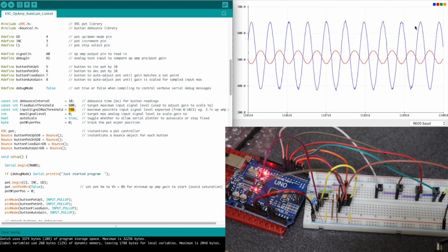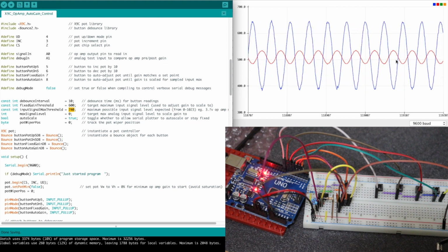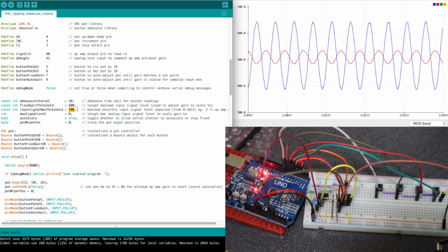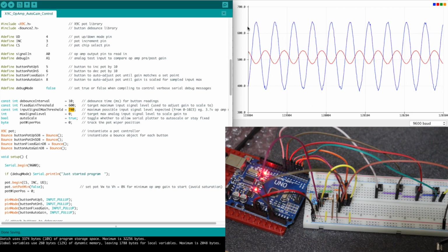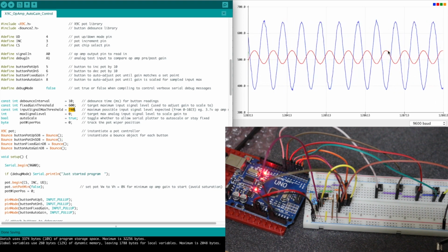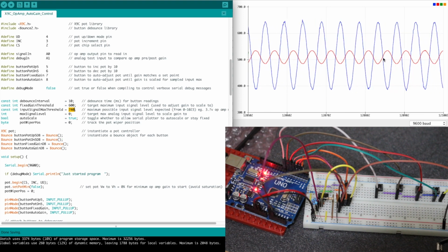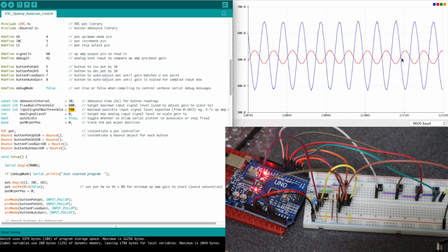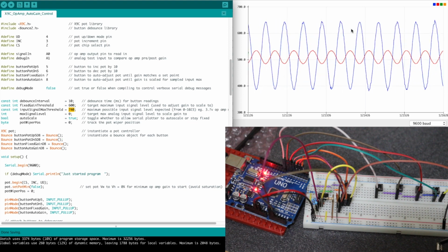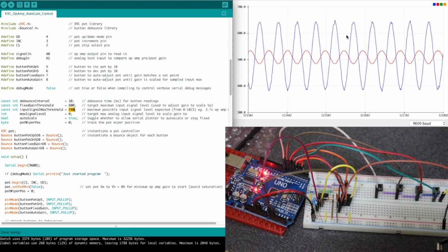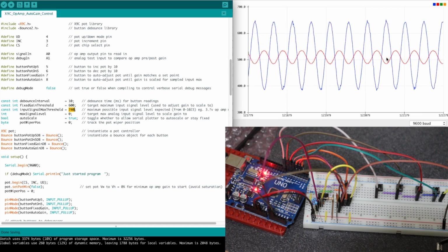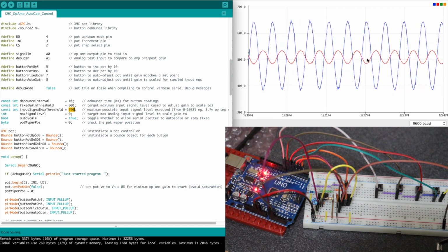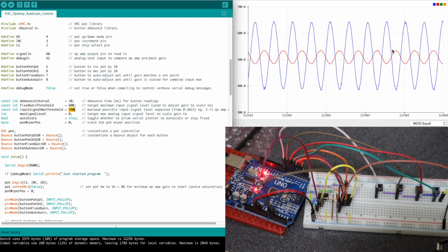It's just that we put in a smaller signal, and now if our full scale capability is 740, we're reading maybe 640 actually. So we've got this new sensor in with only half of the output capability on it. We want to use this generic circuit to rescale this so we can get a full scale input targeting 740. So this is our test signal. We're activating the sensor, knowingly getting our maximum and minimum out of it so that we can calibrate.